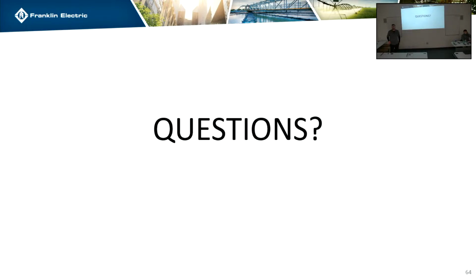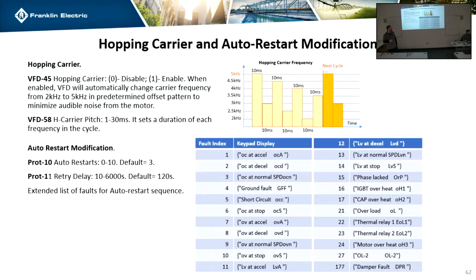In that frequency hopping, is that the same as switching the timing of it? If you have noise coming out of your motor, that god-awful scream it does, you can adjust that? Is that only adjustable up to 5? The hopping did show 5, but the carrier frequency is adjustable up to like 14 kilohertz. You can go higher if you needed to. I think the default was just using 5 as a reference, but the drive goes much higher than that as settings. You could go to 6 or 8, definitely.